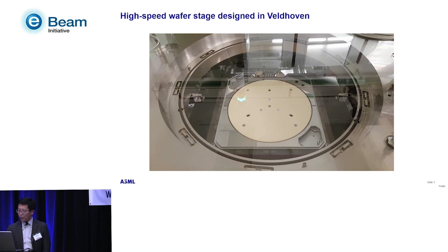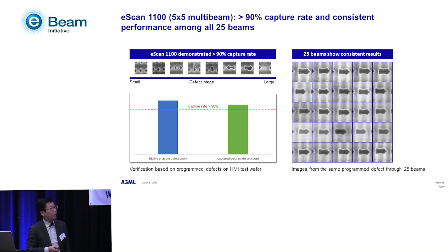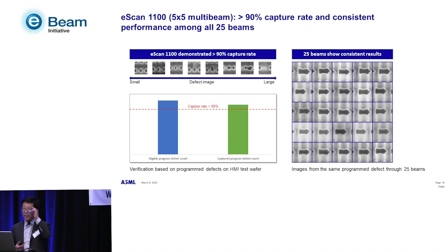On the results side: we demonstrate a capture rate greater than 90% on a standard HMI test wafer, looking at all programmed defects intended to be captured. The 25 beams show uniformity in their imaging capabilities.